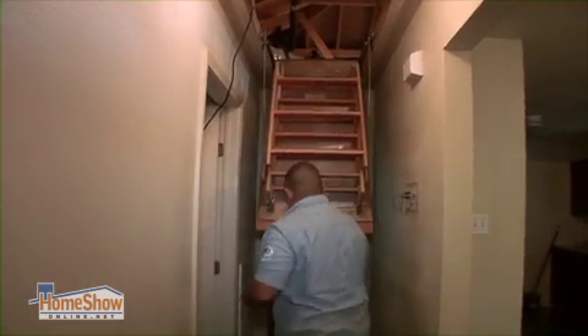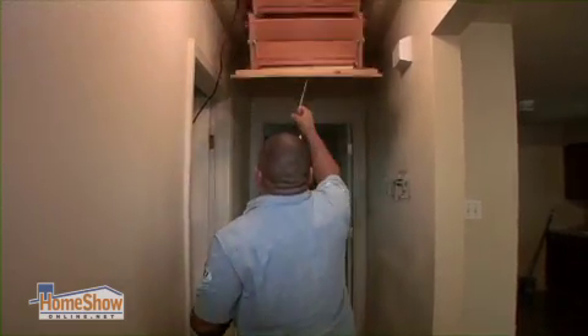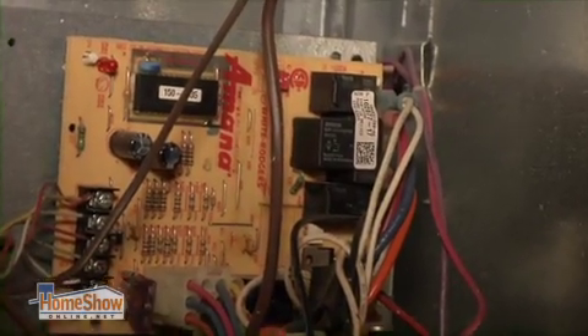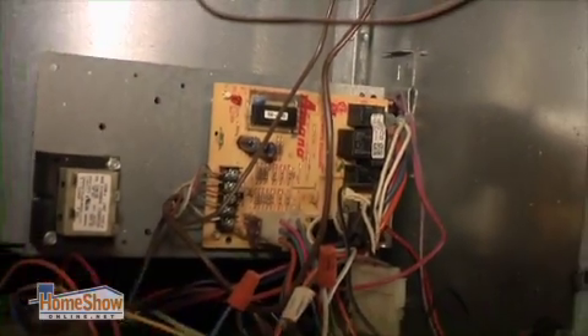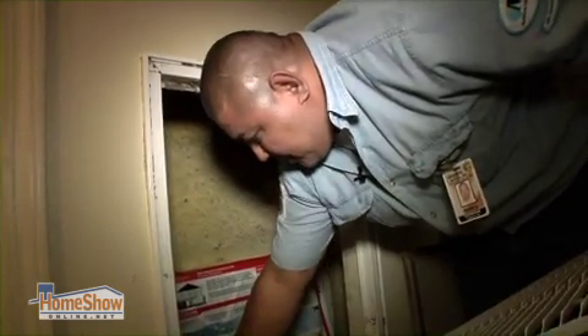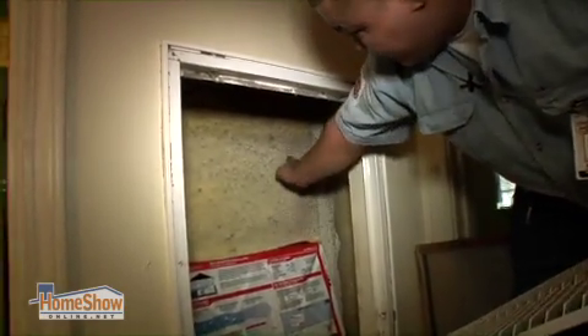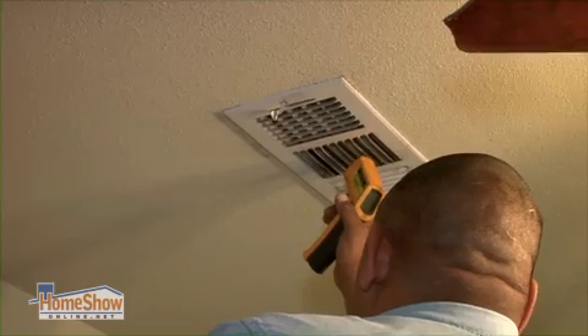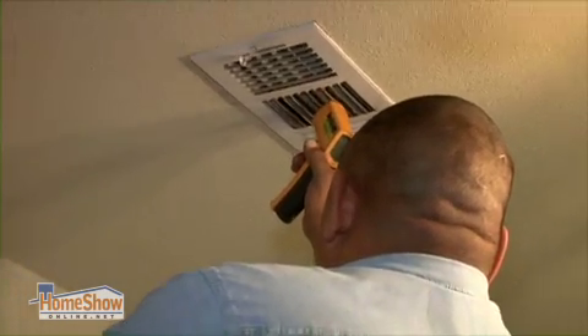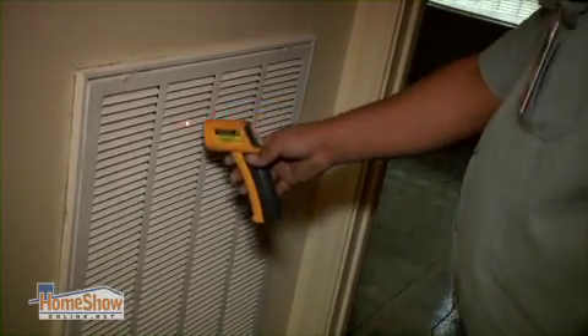What I've done today is performed a 19-point maintenance efficiency inspection on the furnace. The rollout switch was defective, and that's why the furnace wasn't operating the way it should. We did find that the system has high static pressure on the return air side. It has a 16-inch duct going to it, which should be a 20-inch duct. Temperature differential across the supply and return was at 56, which is in range. The furnace is now operating properly.